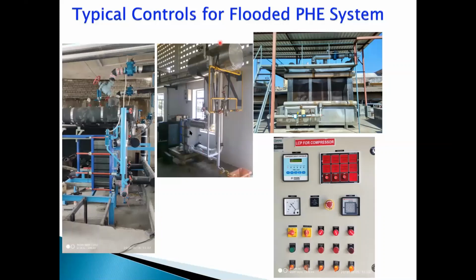This is another plate type heat exchanger. This one is with a U-type heat exchanger connection. This is with a typical accumulator connection. You have a float system. You have a solenoid valve system, which maintains the liquid. You see, the function of this level control is to maintain a constant level of ammonia in this PHE, to keep it flooded so that you get maximum heat transfer and efficiency.